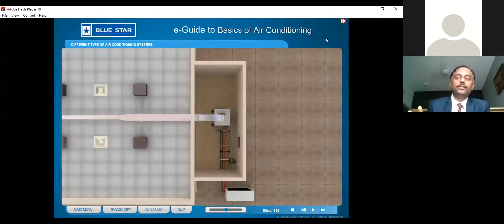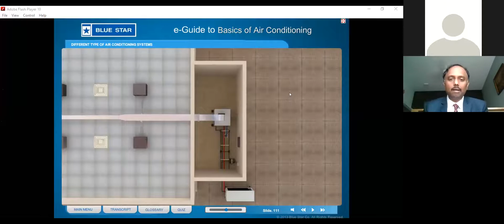This is a very important category. Both ducted split air conditioners and floor mounted packaged air conditioners have machines with inverter technology. Inverter compressors are 25 to 30% more energy efficient compared to normal package units or split air conditioners. The power savings works out to around 2,500 rupees per ton per annum, meaning the additional cost invested can be recovered in flat 10 months.